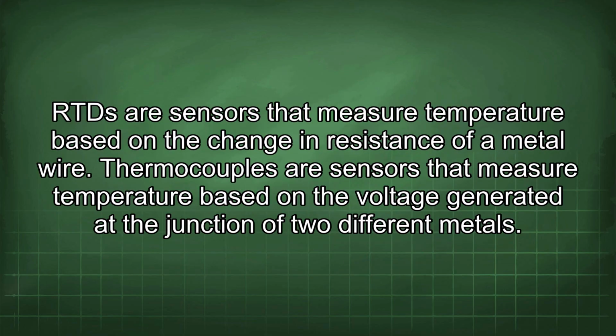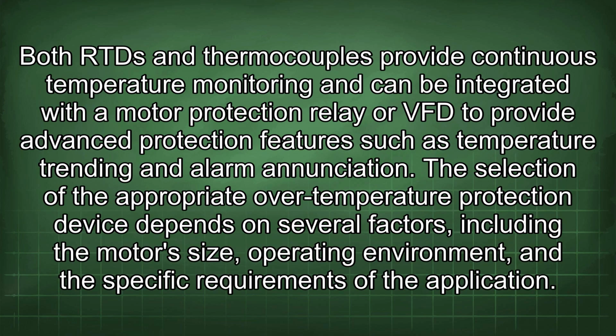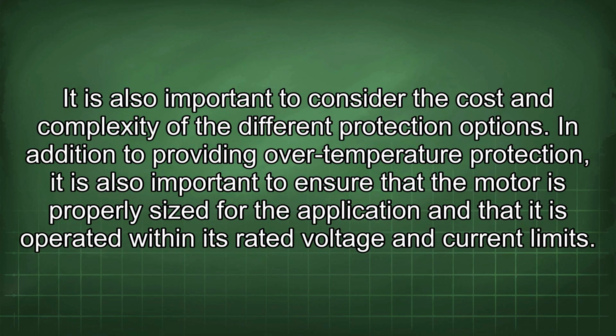RTDs are sensors that measure temperature based on the change in resistance of a metal wire. Thermocouples are sensors that measure temperature based on the voltage generated at the junction of two different metals. Both RTDs and thermocouples provide continuous temperature monitoring and can be integrated with a motor protection relay or VFD to provide advanced protection features such as temperature trending and alarm annunciation. The selection of the appropriate over-temperature protection device depends on several factors, including the motor size, operating environment, and the specific requirements of the application. It is also important to consider the cost and complexity of the different protection options.